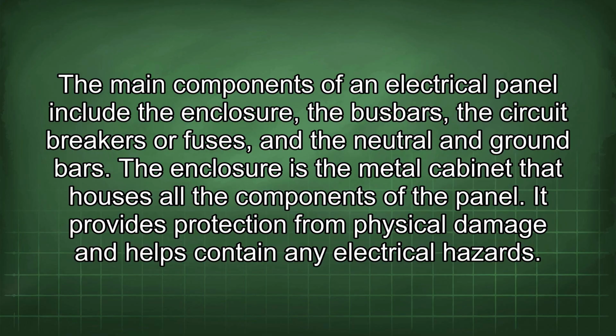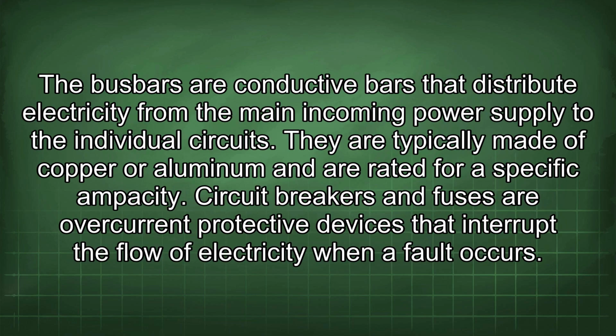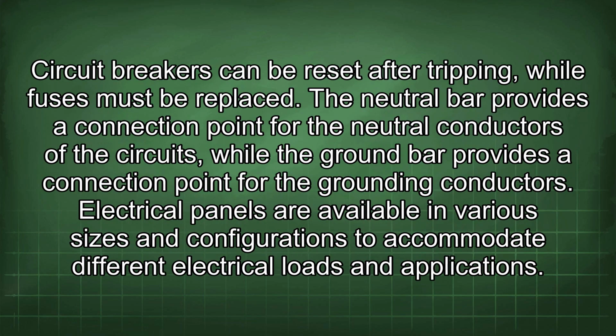It provides protection from physical damage and helps contain any electrical hazards. The bus bars are conductive bars that distribute electricity from the main incoming power supply to the individual circuits. They are typically made of copper or aluminum and are rated for a specific ampacity. Circuit breakers and fuses are overcurrent protective devices that interrupt the flow of electricity when a fault occurs. Circuit breakers can be reset after tripping, while fuses must be replaced. The neutral bar provides a connection point for the neutral conductors of the circuits, while the ground bar provides a connection point for the grounding conductors.